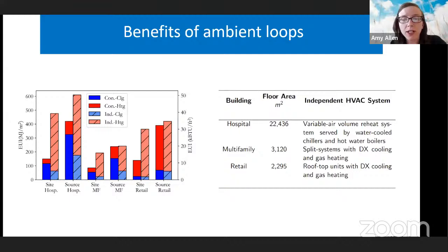And this ambient loop configuration did not result in a great deal of heat rejection or sharing of heat among buildings, which I can discuss in more detail if there's interest. But it did result in a significant EUI reduction for this individual building type. And because of the dominant nature of the hospital building's load, that also resulted in an overall EUI reduction at the district level, which points to the benefits of these systems for individual buildings and districts in which significant thermal load diversity exists. And I selected these prototypical building types based on a load diversity metric on an annual basis that was proposed by Zarin Pass and others in a 2018 paper.